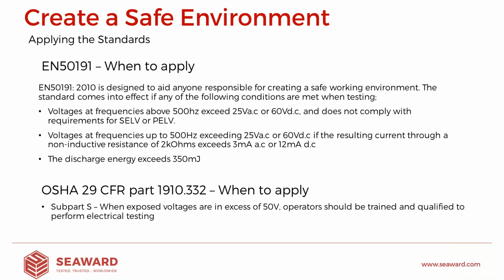So how does that relate back to what we do in terms of a production line test? Well, firstly, those of you that are involved in that will pretty soon realize that most of the tests we do, particularly the high pot dielectric withstand tests, are typically 1000 volts or greater. Generally, they are AC at 50 or 60 Hertz, or we do DC ones, which are at much higher voltage levels. So we know that we're ticking the box in terms of the voltages. Could the resulting current flow through a non-inductive resistance of 2000 ohms?